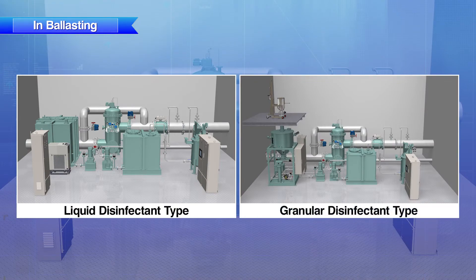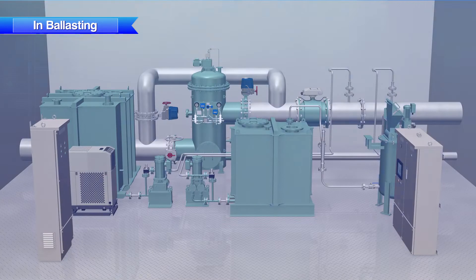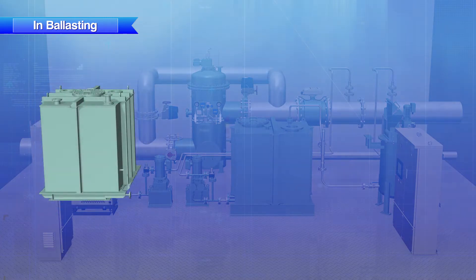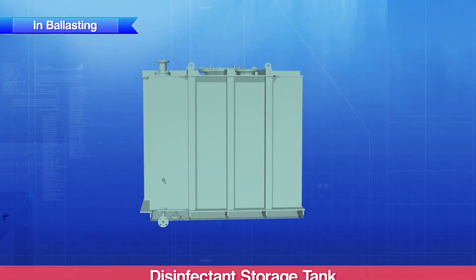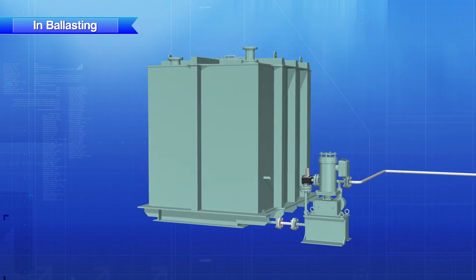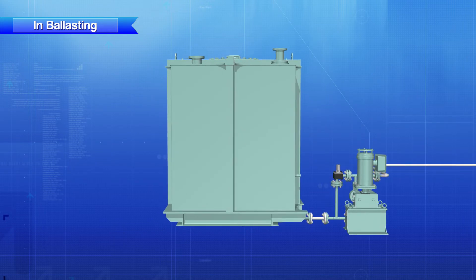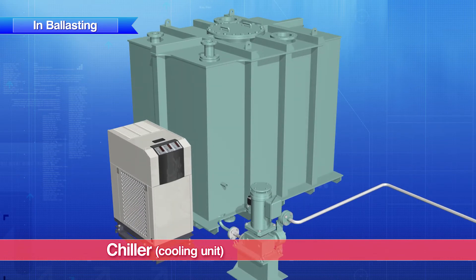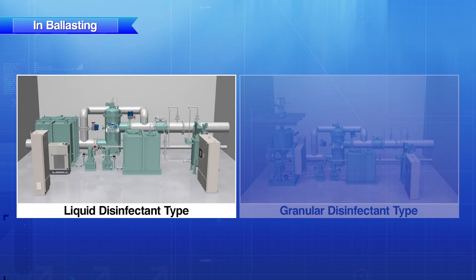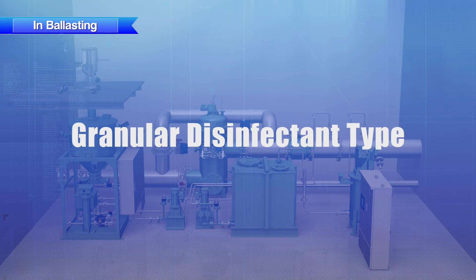Now let's look at the difference in components and chemical injection process for each type of disinfectant. For the liquid disinfectant method, the liquid disinfectant stored in the disinfectant storage tank is pumped by the chemical injection pump and injected into the ballast water line. The disinfectant storage tank is equipped with a chiller — a cooling unit that prevents deterioration.